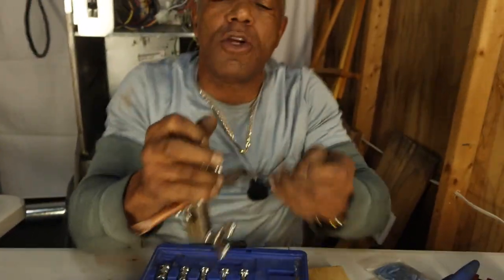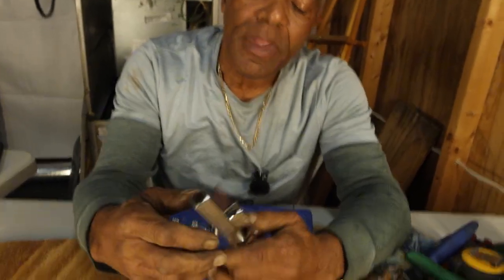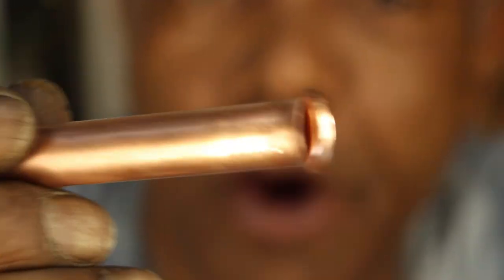This all still seems a little strange to you, but as the class goes on, I'm going to show you a flare nut. I'm going to show you, once you get that end of that copper flared, how there are connecting pieces that will connect, and I don't have to braze the copper. See, there's several different ways that we can connect our copper. We can use flare nuts, and then we don't have to put heat on it. We don't have to put a torch on it. We don't have to braze it.